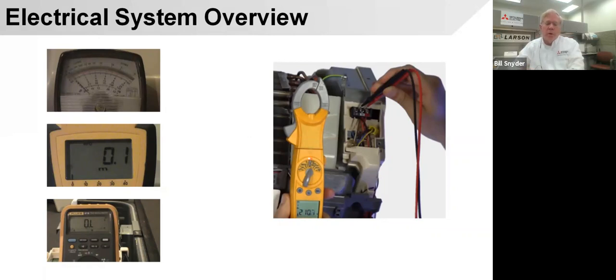Between 2 and 3, though, is a pulsing DC voltage. And depending upon what type of meter you have, they react differently. So if you have one that's working fine, I would suggest you take your meter out there and see what type of DC voltage you're seeing between 2 and 3, and just see how your meter works. This top analog meter, I'm old enough that I have an analog meter, and it actually reads this DC pulsing voltage the best. The needle bounces up and floats around, and you can see what's happening.